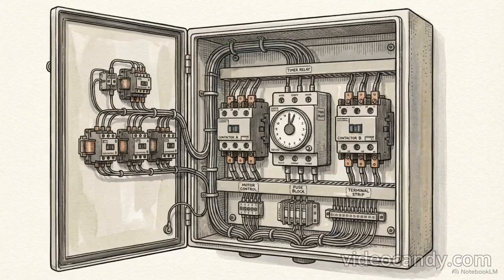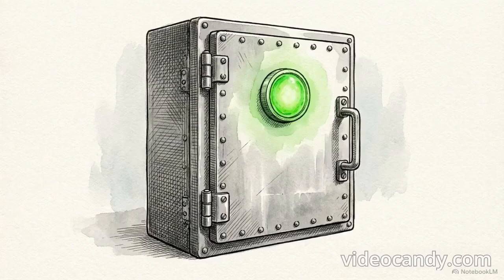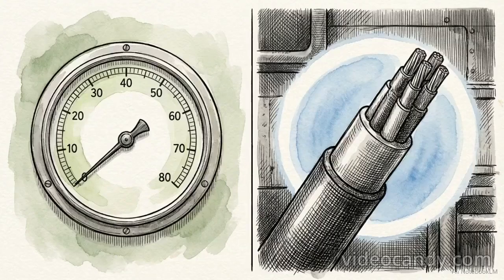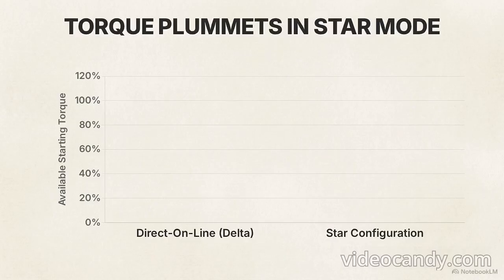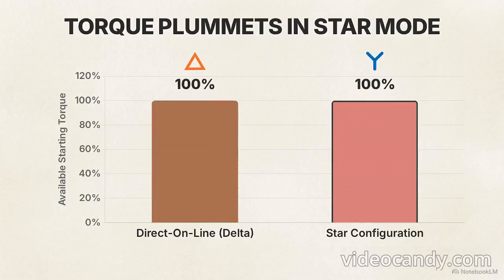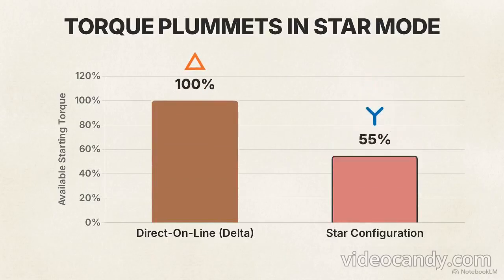To prevent catastrophic operator error, the panel features a strict mechanical interlock. This prevents the handle from being manually forced into the delta run position before the motor has properly accelerated. The command circuit acts as the brain of the assembly, ensuring that the transition between these 2 electrical states is perfectly timed. It keeps the system mechanically isolated and continuously protected.